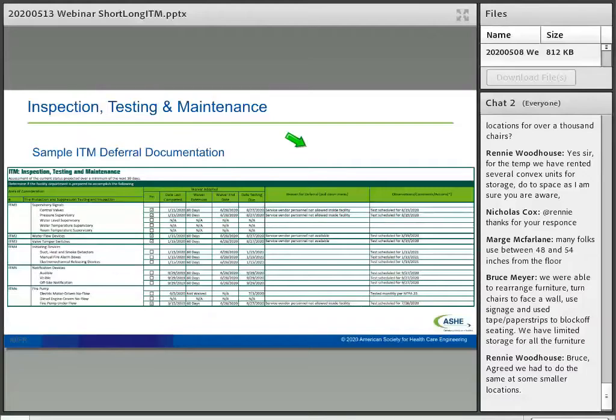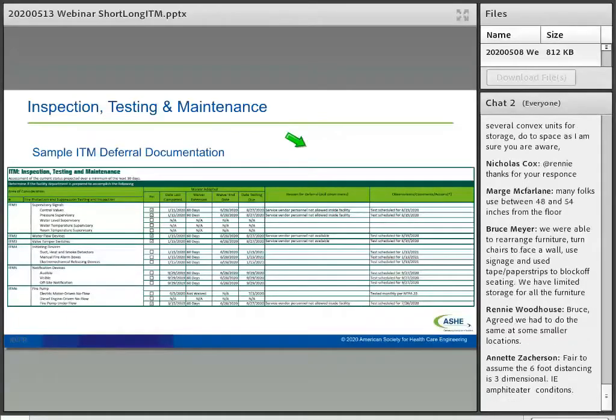Water flow devices, very similar, these are semi-annual testing. Supervisory signals, I should have mentioned, are quarterly testing, required quarterly. Water flow is semi-annual, same thing: tested on January 15th, 60-day extension, waiver end date 6/28, so due August 27th.